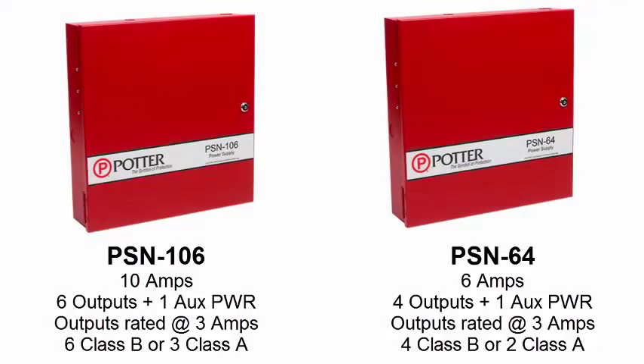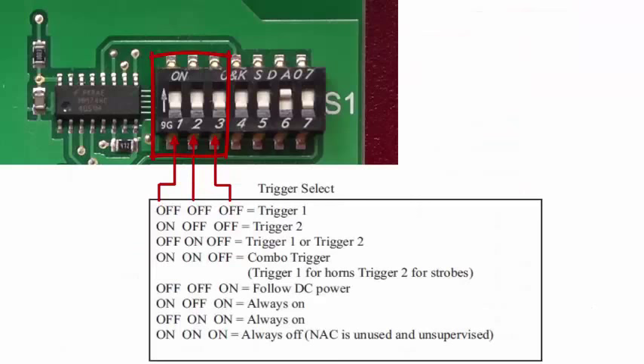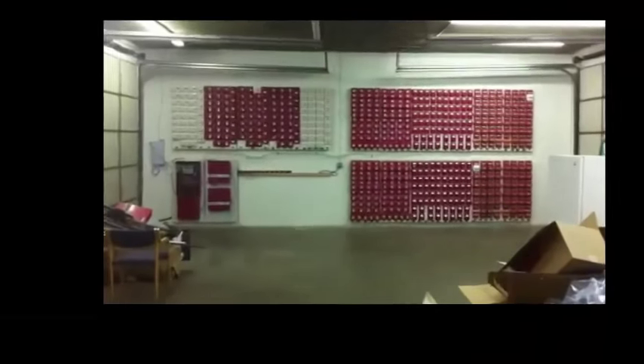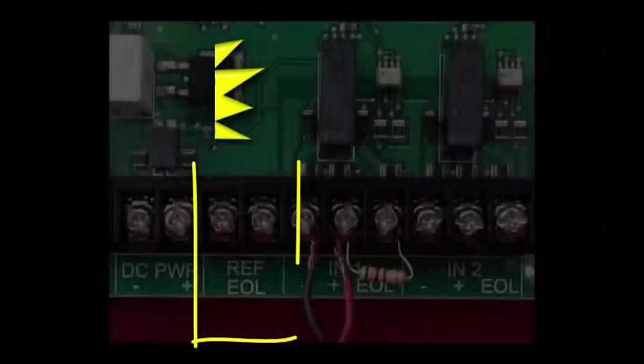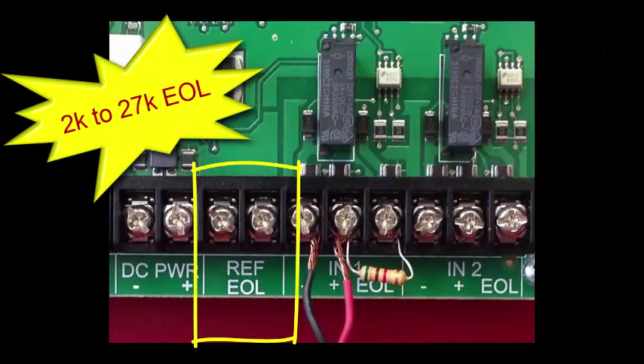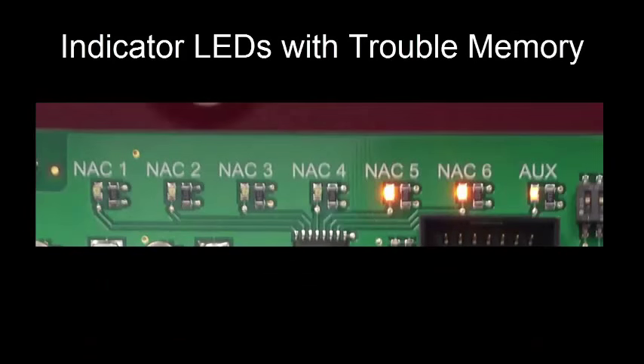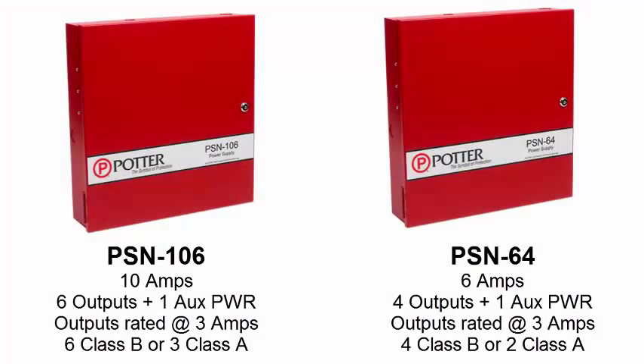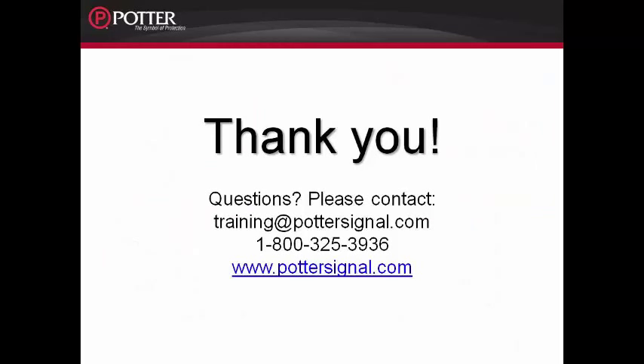To recap, the PSN power supply comes in two sizes, a 10 amp with 6 notification circuits and a 6 amp with 4 notification circuits. The notification circuits are programmed via DIP switches and can be programmed for quadrasync if needed. There is a reference end of the line which can save considerable time when replacing an existing power supply. There is also a trouble memory LED for each NAC output that can also save time in troubleshooting the power supply. This feature rich power supply provides plenty of versatility to save you time and money on your next installation. For more information, please visit our website www.pottersignal.com Thank you.